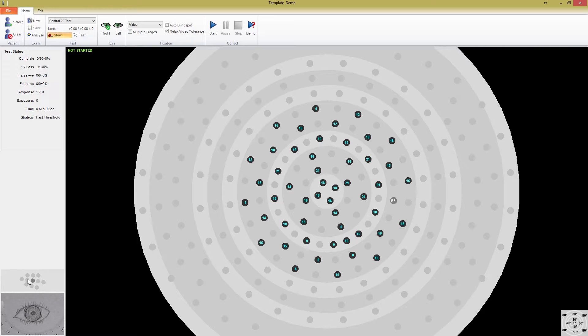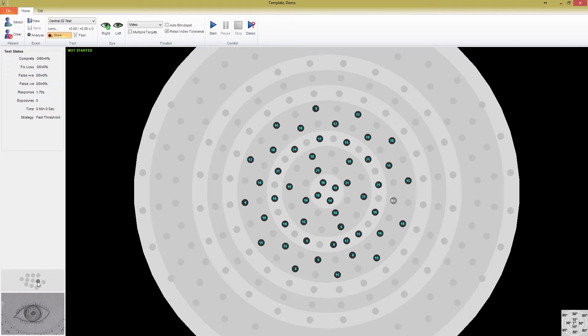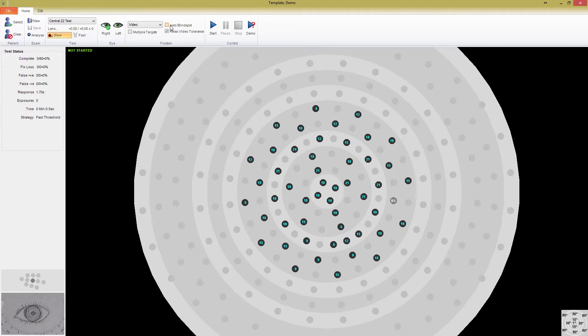With this option turned off, the technician is responsible for selecting the blind spot location, which you can use by clicking on different stimulus locations. However, you should be careful about turning this feature off, as the test will continue even if the blind spot is not correct and can compromise your test reliability and repeatability.